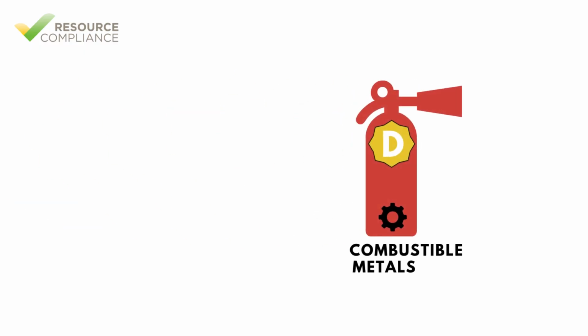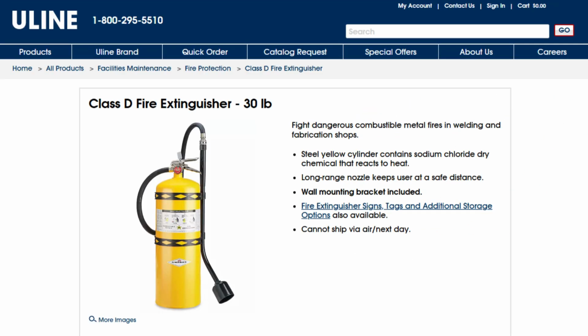Fires involving combustible metals are categorized as Class D. These fires involve reactive metals like magnesium, sodium, potassium, titanium, or lithium. Special dry powders designed to smother metal fires without reacting with them are used to extinguish Class D fires. Class D fire extinguishers are marked with a yellow star with a D inside.